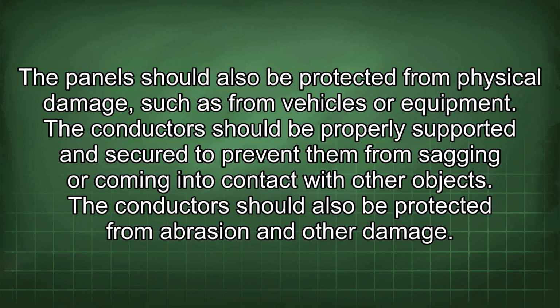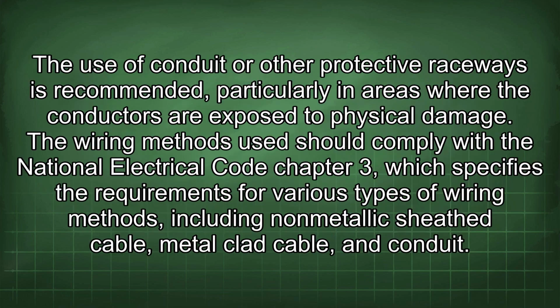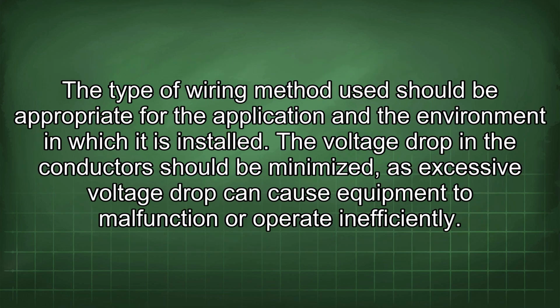The conductors should be properly supported and secured to prevent them from sagging or coming into contact with other objects. The conductors should also be protected from abrasion and other damage. The use of conduit or other protective raceways is recommended, particularly in areas where the conductors are exposed to physical damage. The wiring methods used should comply with the National Electrical Code Chapter 3, which specifies the requirements for various types of wiring methods, including non-metallic sheathed cable, metal-clad cable, and conduit. The type of wiring method used should be appropriate for the application and the environment in which it is installed.